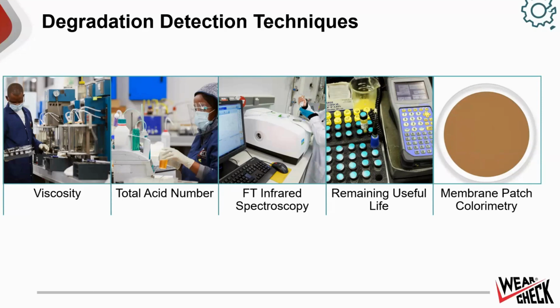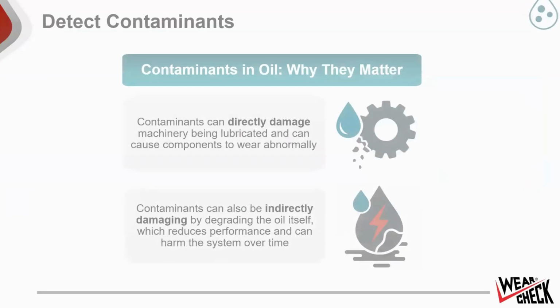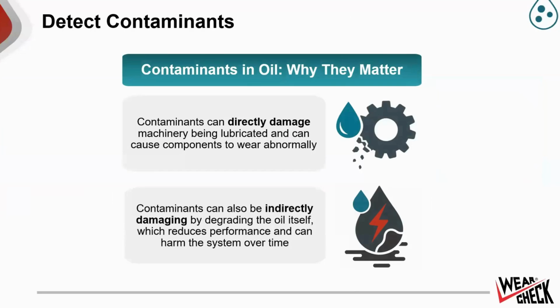And then finally, you have MPC, or membrane patch colorimetry. And this test basically measures the potential for varnish formation in the lubricant as a result of oxidation. It does this by quantifying the amount of, let's call them insoluble color bodies present inside the oil. So those are the main laboratory techniques that most labs use for detecting oil degradation.